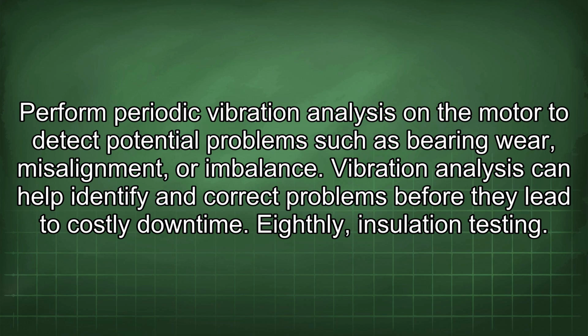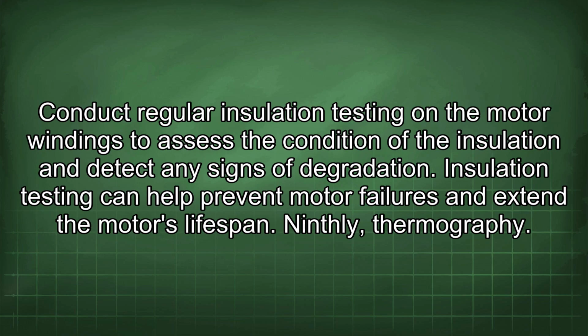Seventhly, vibration analysis. Perform periodic vibration analysis on the motor to detect potential problems such as bearing wear, misalignment, or imbalance. Vibration analysis can help identify and correct problems before they lead to costly downtime. Eighthly, insulation testing. Conduct regular insulation testing on the motor windings to assess the condition of the insulation and detect any signs of degradation. Insulation testing can help prevent motor failures and extend the motor's lifespan.